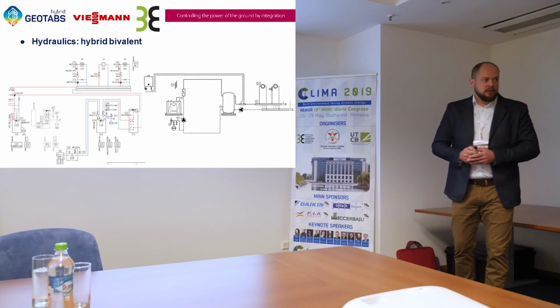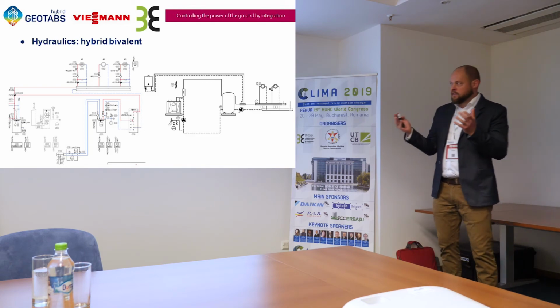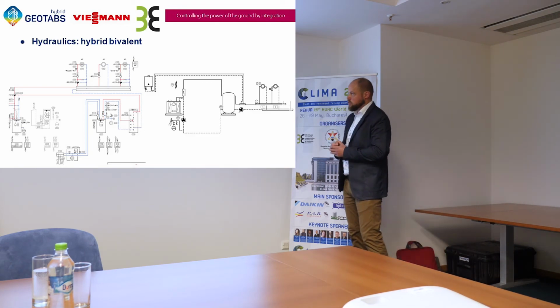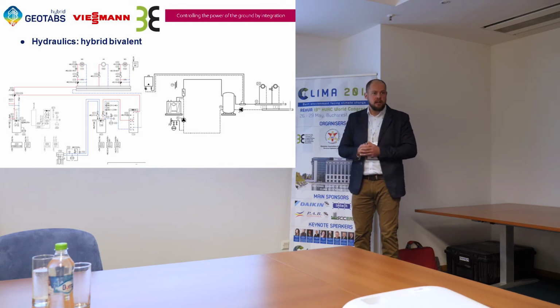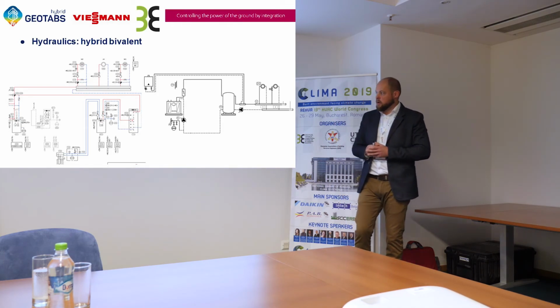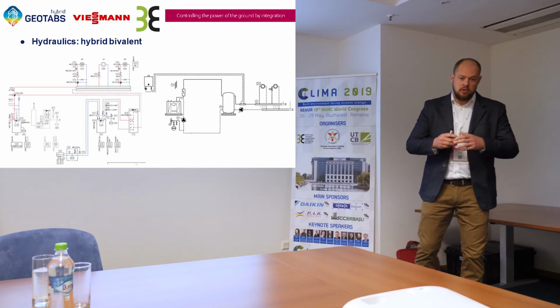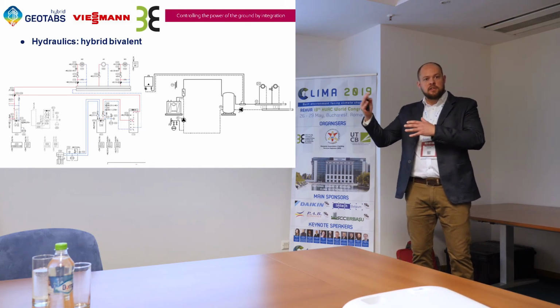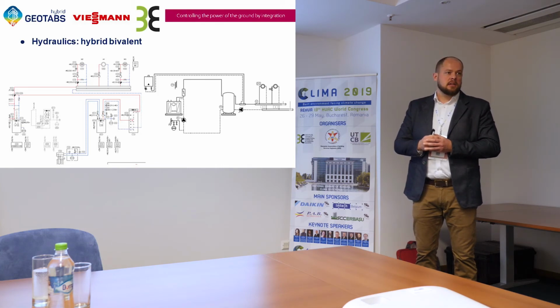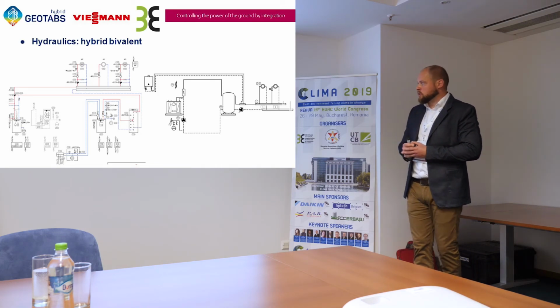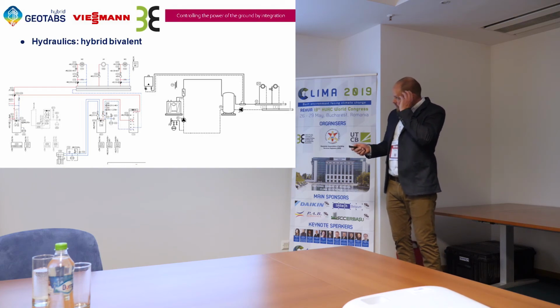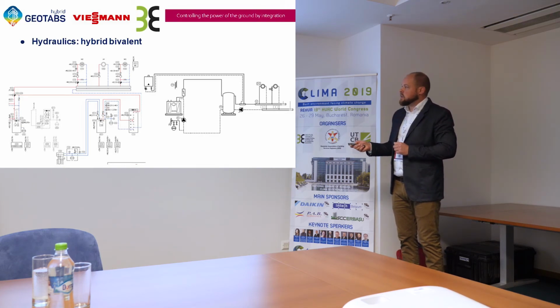How do we make a hybrid installation? In my eyes, a hybrid installation is an installation combined with a gas boiler, for example. So when we have a heat pump of about 40% of the total load, we need another device that can cover the other 60% when needed. So in this case, how do we couple the two systems? In the picture, or the schematics here, you can see the heat pump is connected to a buffer tank on the underside of the buffer tank, and we have a gas boiler or oil boiler or something else. It's connected on top of this buffer tank.